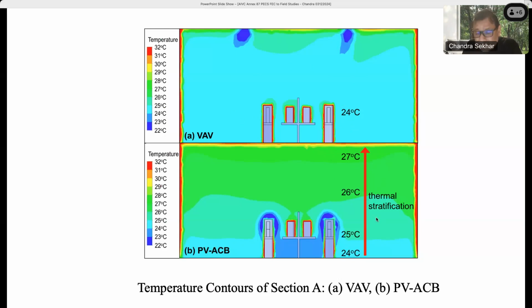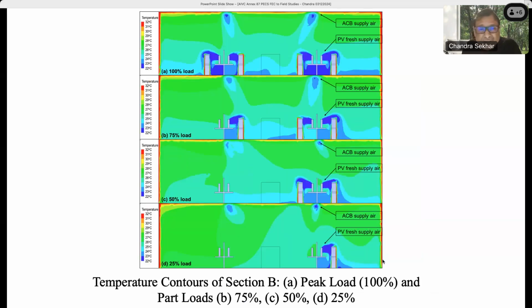By that, even contaminant stratification would take place. We noticed benefits at 100% load, 75% load, and as the load reduces, when you don't have people, you can literally turn it off completely, but we don't want to do that. Certainly we can reduce it significantly. However, where there is a person seated, the localized personalized ventilation really works well in the microenvironment of that zone.